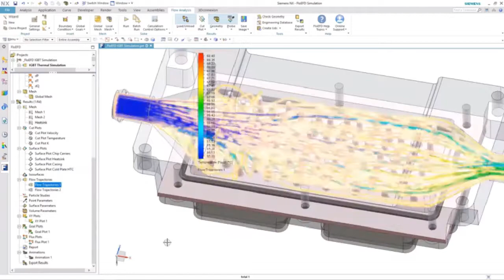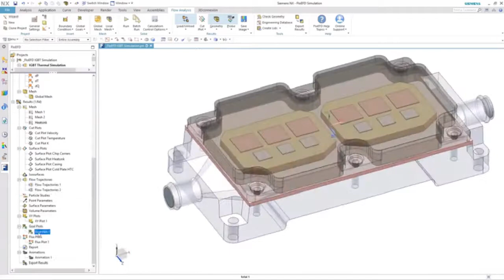From the results, we can see that the IGBT temperatures exceed the required operating conditions. We could easily modify the pins from the expressions, increase the surface area with the fluid, and reduce chip temperature. However, this would increase the pressure drop. The designer would have to iterate through the variables, essentially shooting darts in the dark and hoping to get a solution that meets all the requirements.